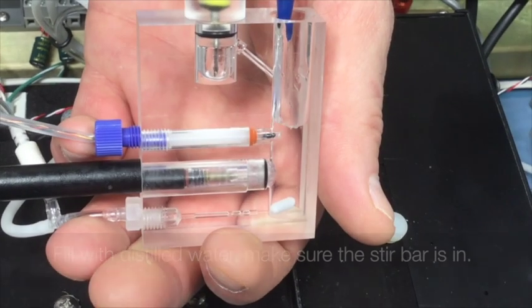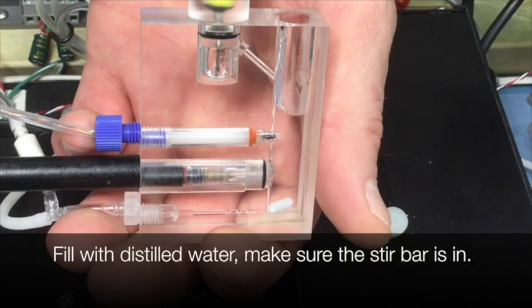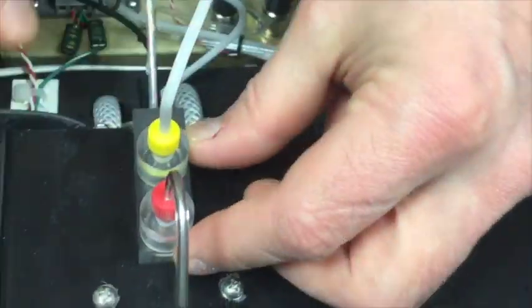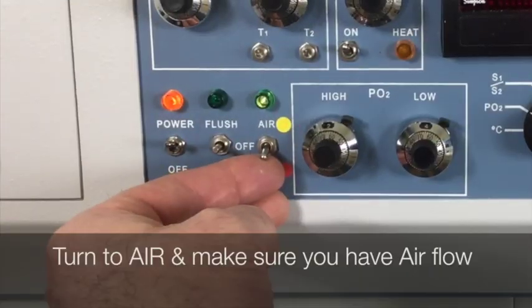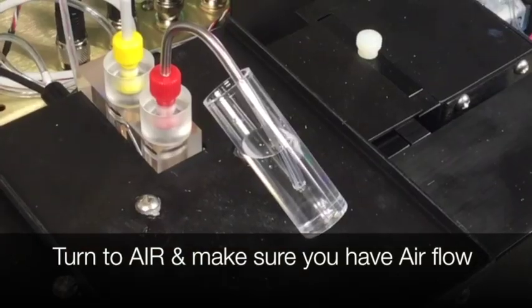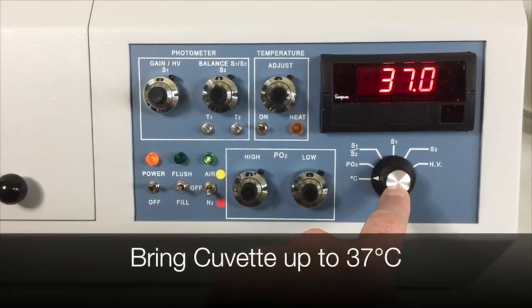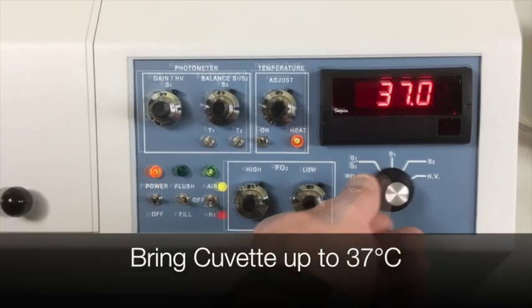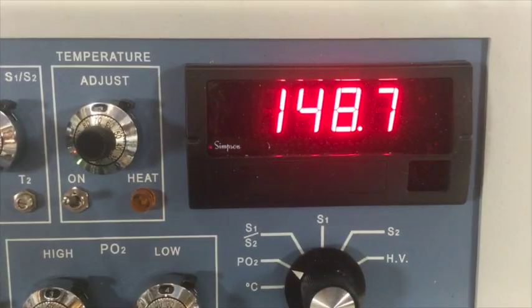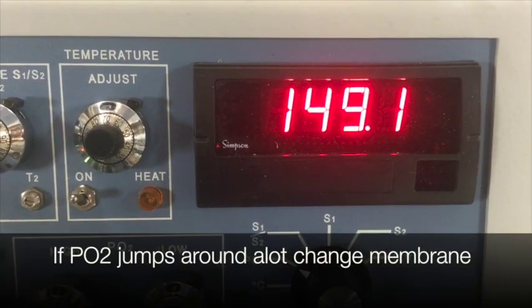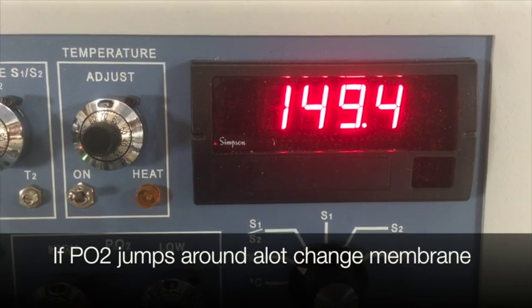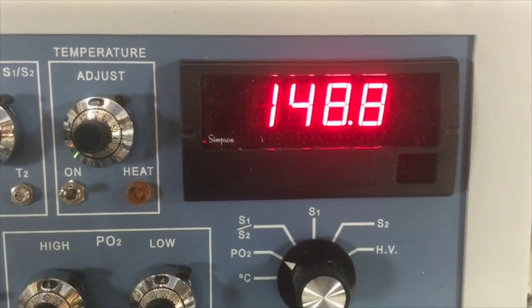How you know your membrane is going bad. Fill your cuvette with distilled water and make sure that your stir bar is in and stirring. Make sure that you have your switch turned to air and that your air is on. After about 30 minutes, your temperature should have stabilized at 37 degrees Celsius. Now turn to PO2 and make sure that that is stabilized as well. If it is really jumping wildly like this video, then you will need to change your membrane.